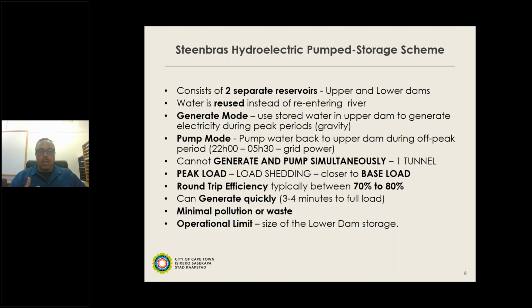Our power station doesn't allow us to do both modes at once — we can only generate or pump, so we're not a dual mode hydro pump station. Tonight at about 10 o'clock we'll switch off from gen mode and change to pump mode, taking power off the grid, which will enable us to move the water now in the lower dam all the way back to the upper dam for use again in the morning.